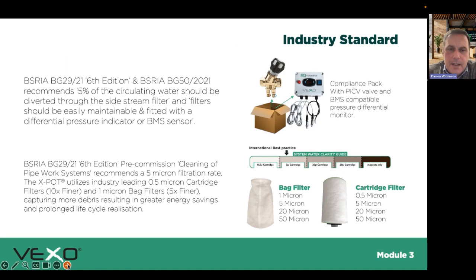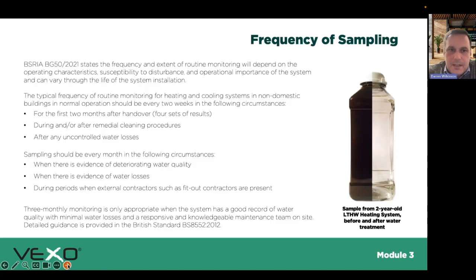BSRIA do recommend, if you are using any kind of filtration for a system, you have some form of alarm system to ensure that you can change that filter when it needs to be changed. If something's difficult to maintain, it probably won't get maintained, or if it's out of sight, it's out of mind. So really key that understanding any equipment you install, if there is a servicing requirement, you make it foolproof so somebody knows they need to come and change it.